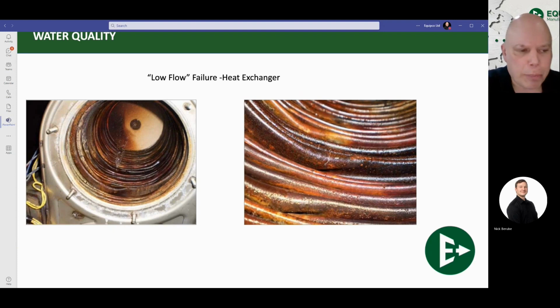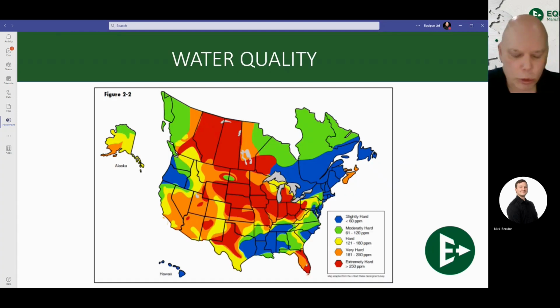So I talked about before, the buildup of the magnetite or dirt or calcium or anything on the system will lead to a low flow situation on our heat exchanger. If we can't move the water through that heat exchanger, we can't scrub away the heat. If we can't scrub away that heat, we're going to get hot spots, and we're going to lead to cracks in our heat exchanger, cracks in our pipes, stuff like that. So here's a little picture of a heat exchanger. This is a water tube where we had a big buildup of magnetite on the inside, which led to a hot spot, which led to a crack on the heat exchanger. This was not a warranty situation. The homeowner had to pay full price for a new heat exchanger because the water quality was bad on this one. So that's magnetite.